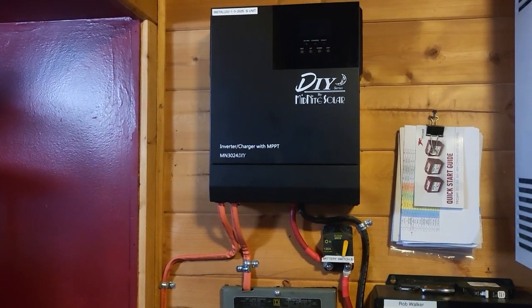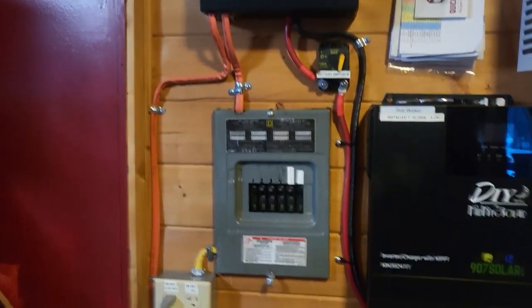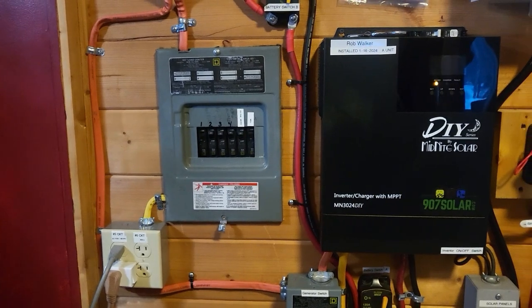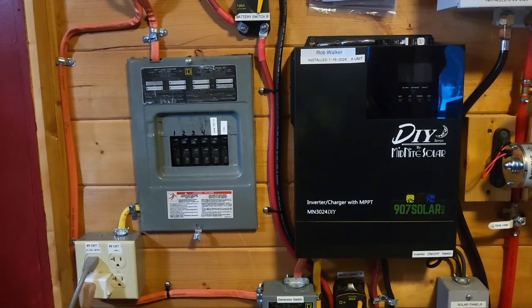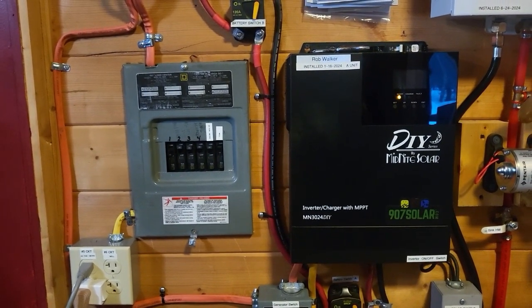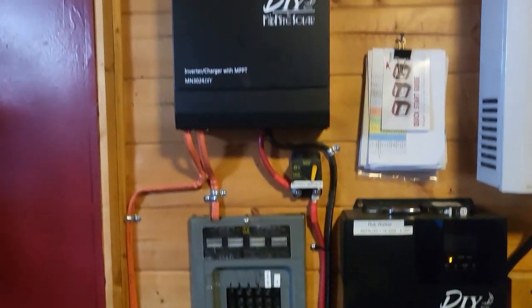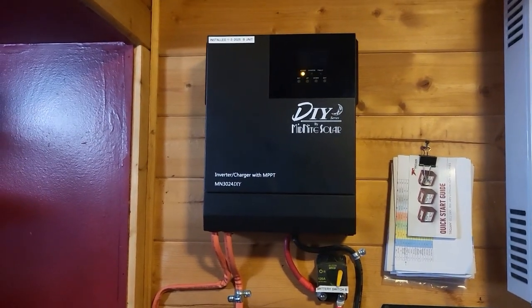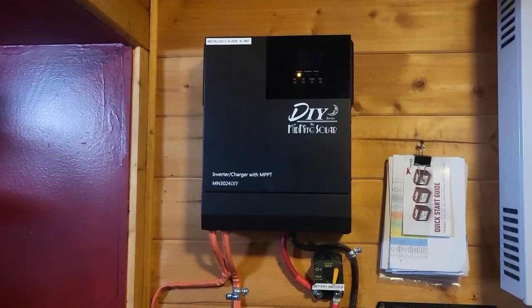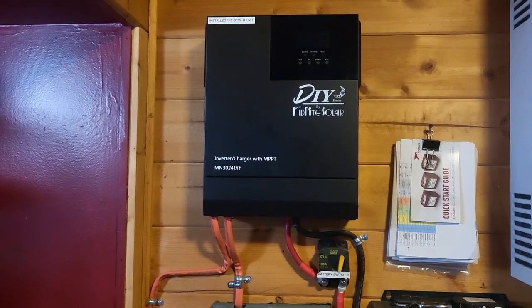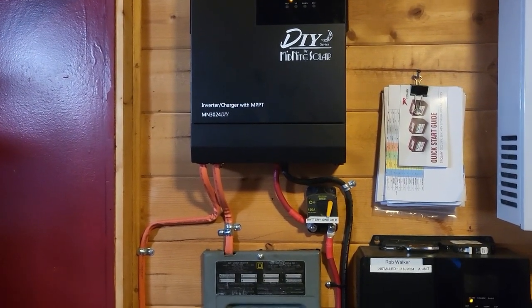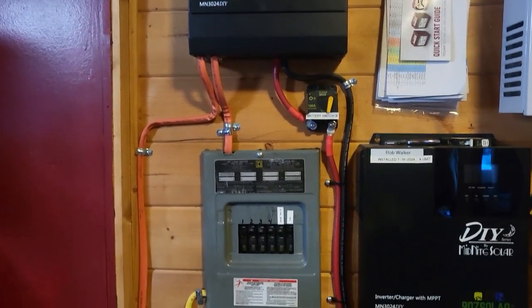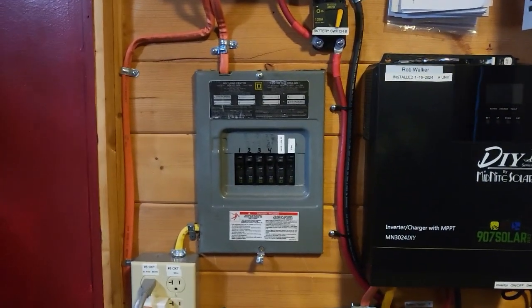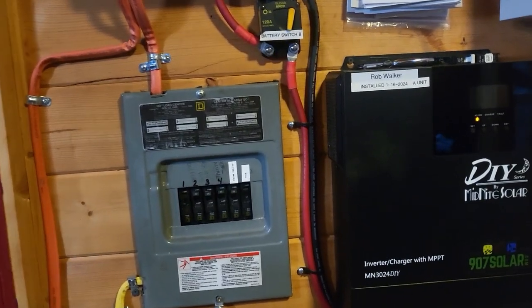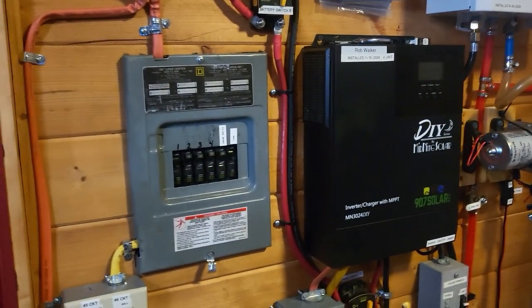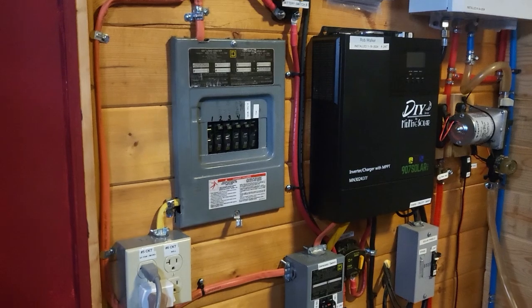It really balances it out. It takes a lot less load off of one inverter, making it run a lot cooler and more efficient. But by doing so, these inverters draw power themselves off the batteries, so in order to compensate for that, I've added another battery. It also gives it a lot more, what would you say, load bank.